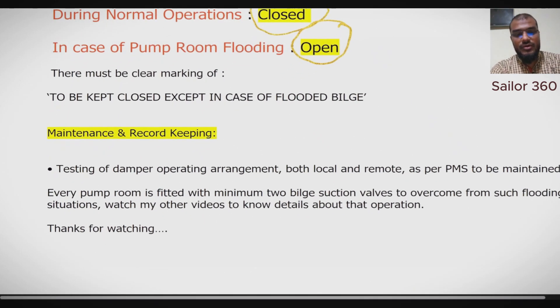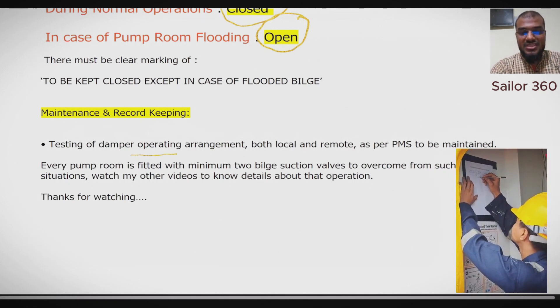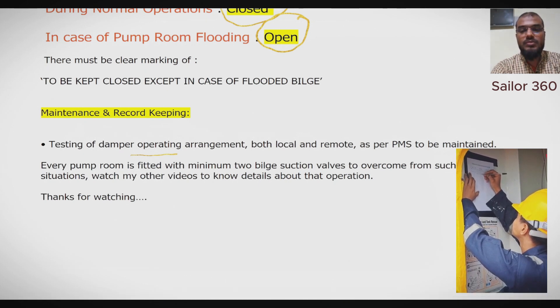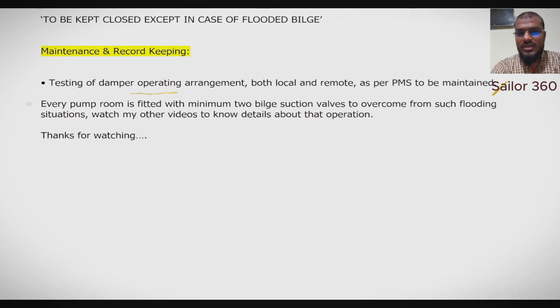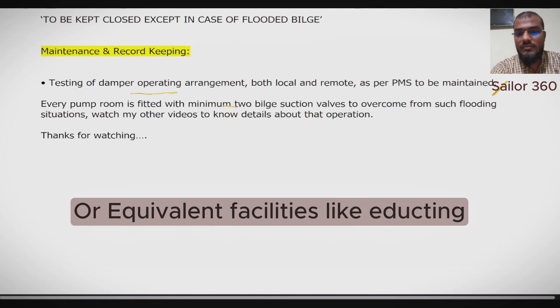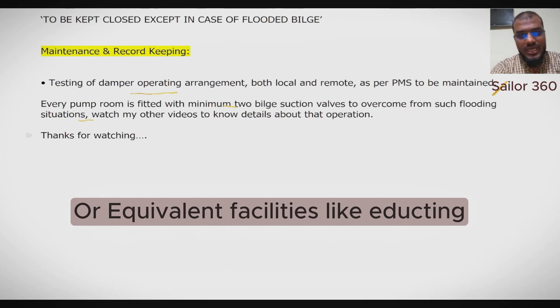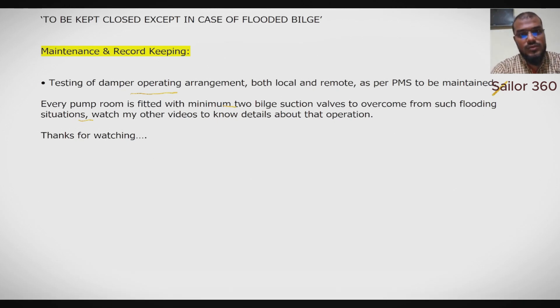Regarding maintenance and record keeping of the flooding damper: testing of the damper operating arrangement — both local and remote — should be maintained as per PMS, following company procedures, and records should be kept. As for the remedy when flooding takes place, every pump room is fitted with a minimum of two bilge suction valves. Fixed bilge pumps are there during flooding situations to assist in pumping out all the flooded water from the pump room.